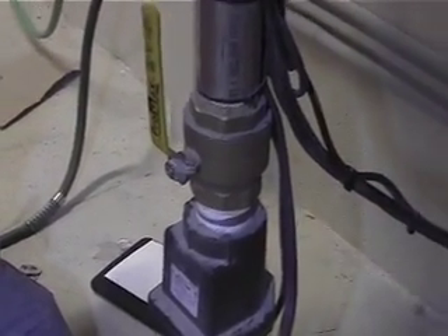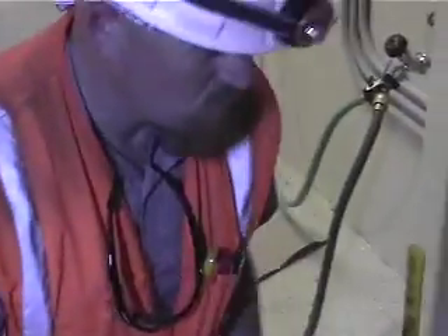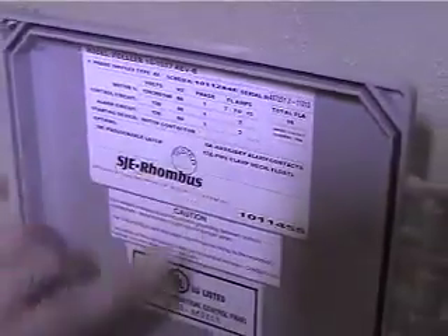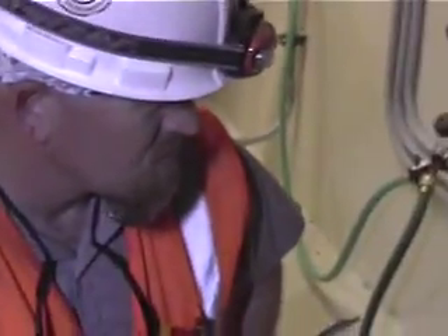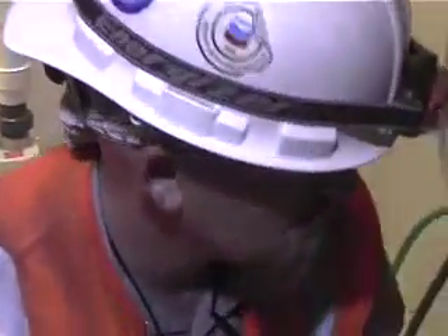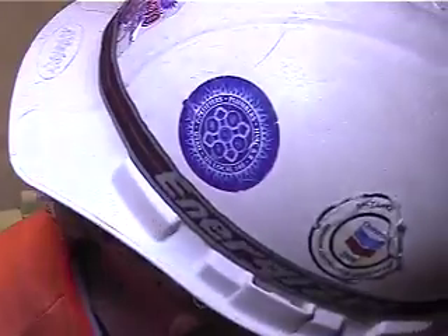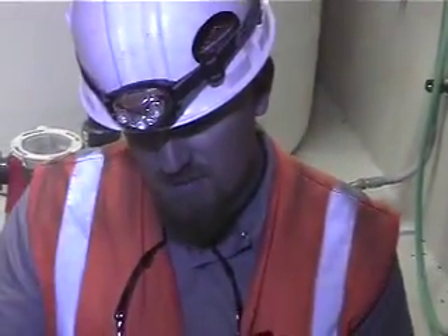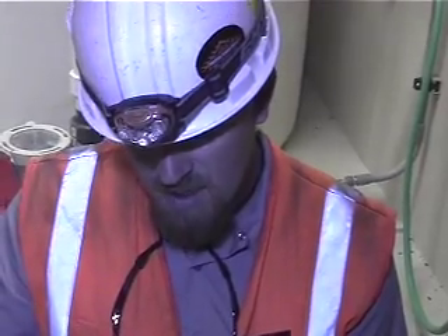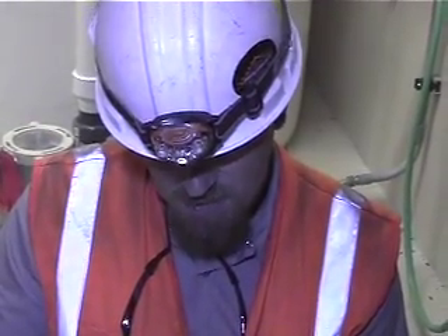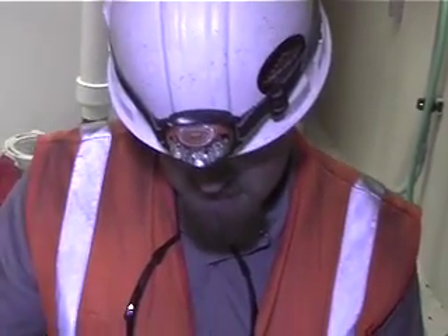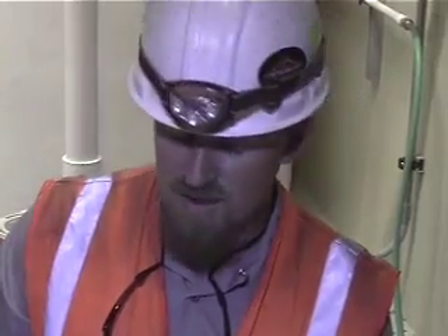To check for amperage on the motor, to clamp amp those, you would clamp onto this black lead right here. Okay, how many amps? It is rated for, control circuit, no, 7 to 15 full load amps. Now that's not the actual motor amperage. Let me see if I have that real quick in my paperwork. I was at 9 amps on L1, 9.1 amps on L2. As for the motor data, I'm going to have to pull up the submittal on this pump to find out what full load amps are actually at, because I couldn't get down to the motor to actually see it.